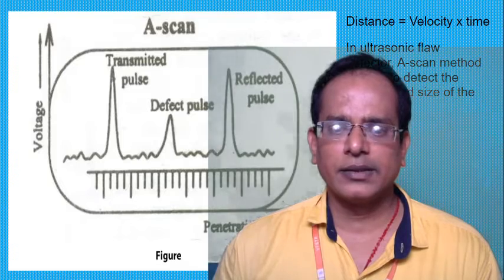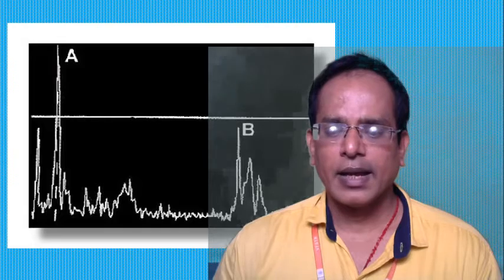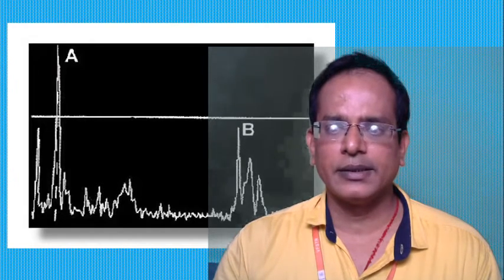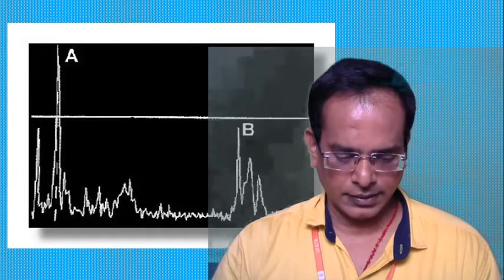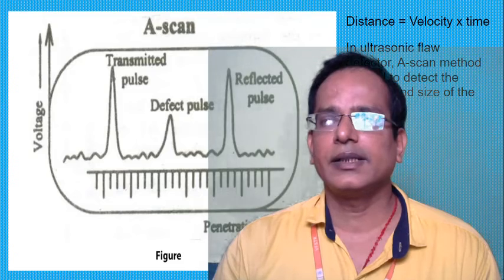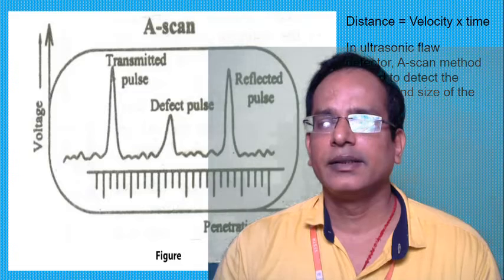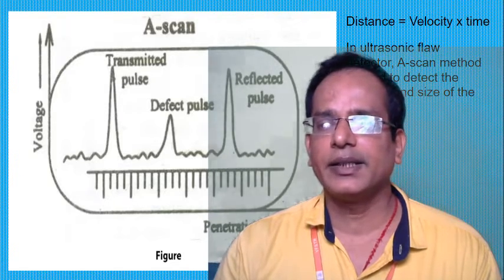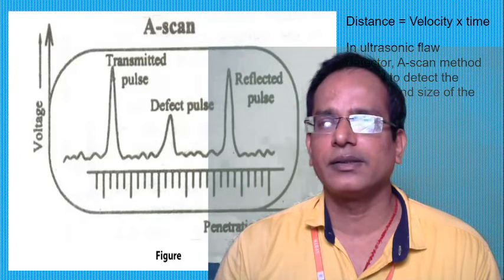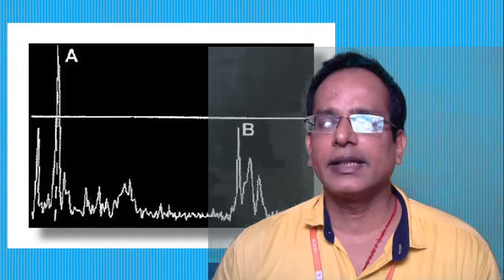The distance is calculated using the formula: distance equals velocity multiplied by time. The ultrasonic flaw detector A-scan method is used to detect the position and size of flaws — a flaw meaning any defective area.